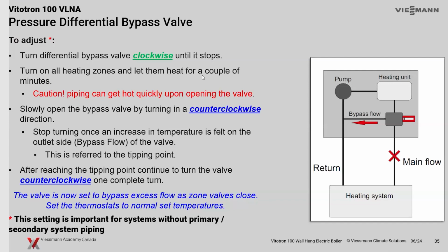So essentially all the zones, meaning that even the one with the highest pressure drop is open and we've got flow. And we're just going to start to close this valve off until we start getting a little bit of a bypass flow going back through the unit here. So we're essentially setting up where, once the zones start to close, this little spring will start to open up a little bit further and we'll have a little bit more bypass flow.